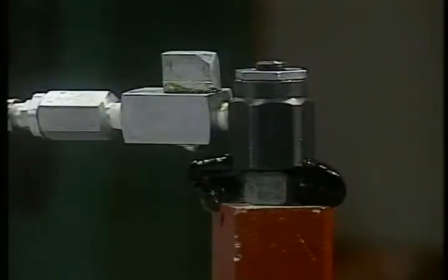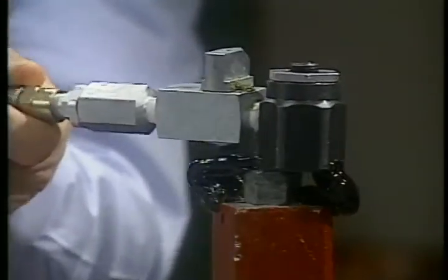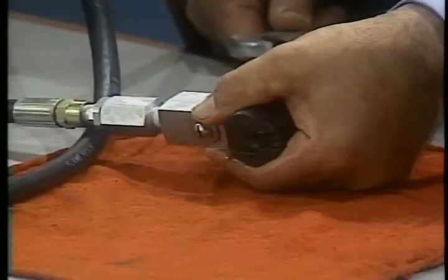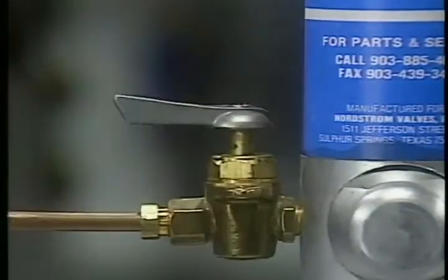If the giant button head coupler is leaking, pressure cannot be generated. Leakage of sealant may occur between the button head coupler and sealant fitting as you inject sealant into the valve. This leakage may come from either the coupler or the fitting. To determine which part is leaking, first remove the button head coupler from the sealant fitting. Then open the hose shutoff relief valve and operate the Hypregun.